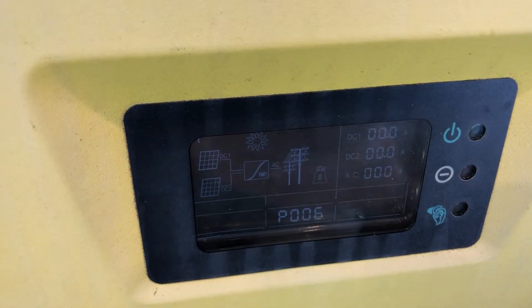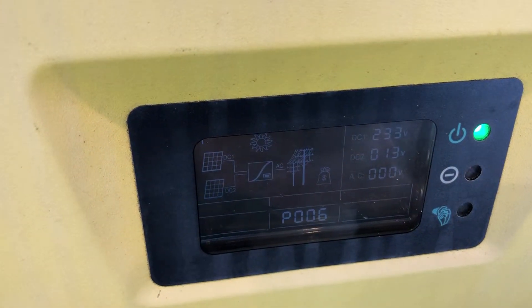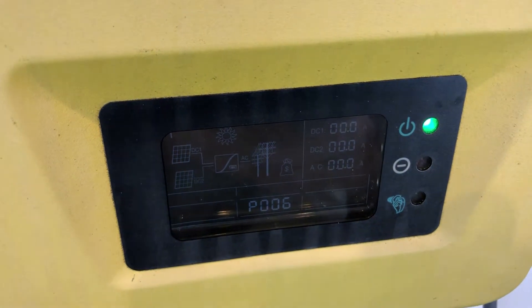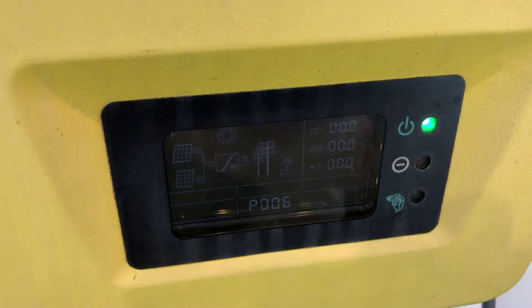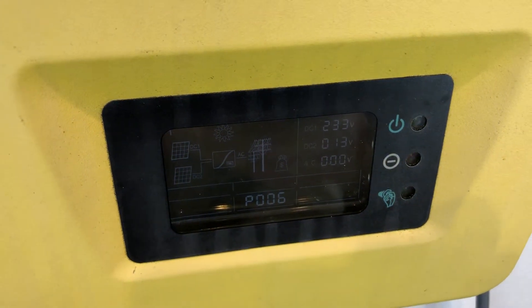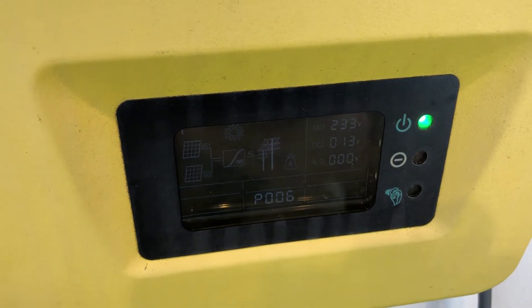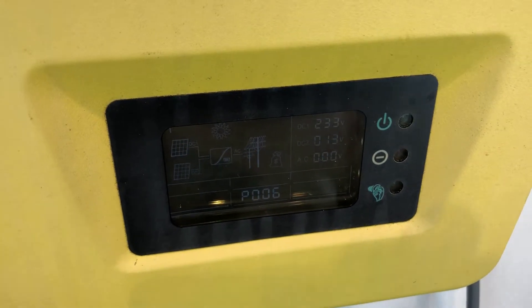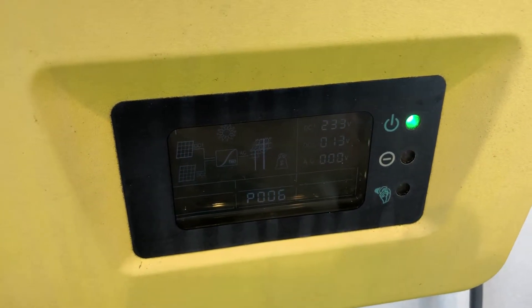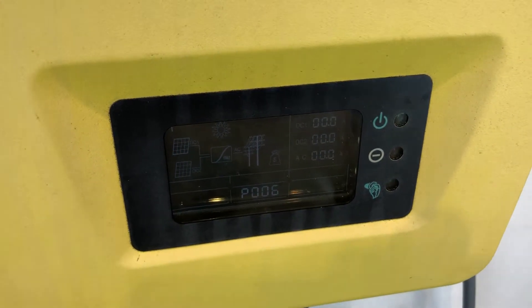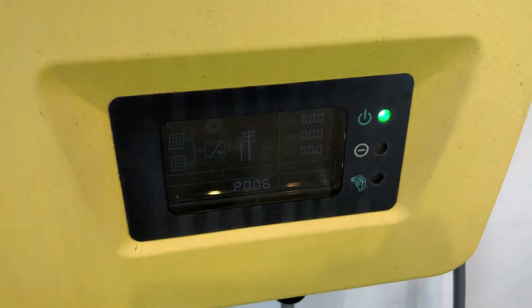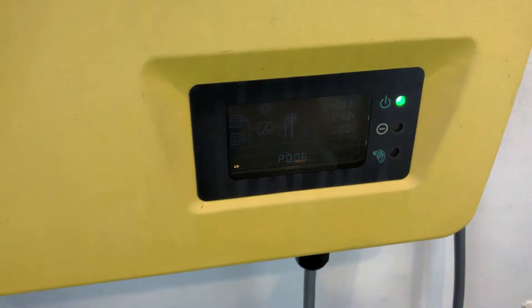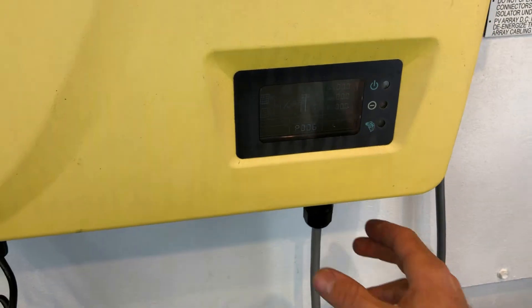...not detecting any power from the grid — it's not detecting the power coming in from the street. So the first thing I would recommend you do if you are seeing the P006 error is check that the AC plug underneath the screen is actually plugged in on the inverter.